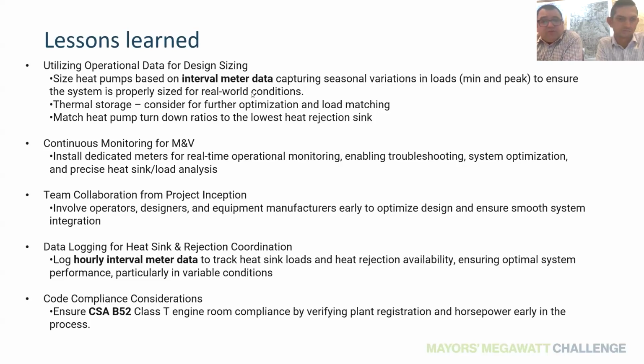The thermal storage, as part of our design, we did review introducing separate thermal storage tanks, but due to capital cost restrictions and pressures, we decided to use, as I mentioned, the building heating loop as an option, which now we actually have to use because it's needed, based on the misalignment between the generated heat and the demand. And the ammonia heat pump size should be properly reviewed with the first item with available capacity, and you can ensure to have the proper turn down ratios, so it's properly sized. Again, the intent is to extract the maximum run hours and efficiency of the system.